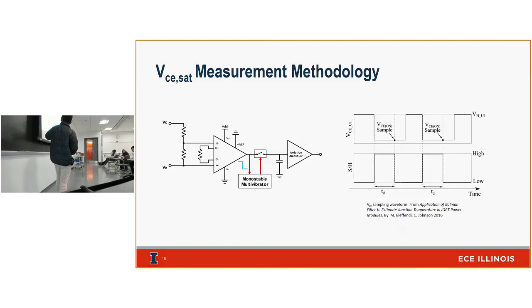So whatever we divide the voltage down by, we can also gain it back up internally. We use this input instrumentation amplifier to basically clamp our output voltage that goes to the rest of our measurement circuitry. So this means that we have maybe a 3 kilovolt DC link voltage, but as that gets divided down and gained back up, at the end it just saturates our instrumentation amplifier, and it gets clamped to the supply voltage of this amplifier.